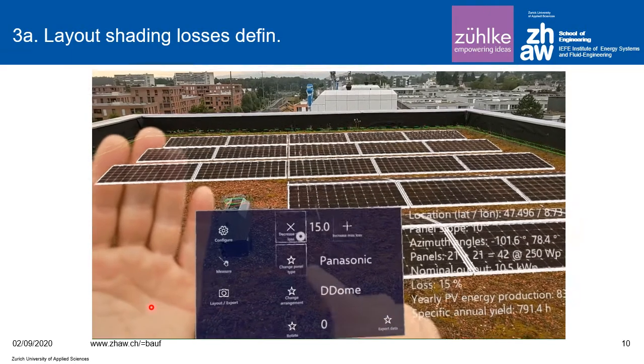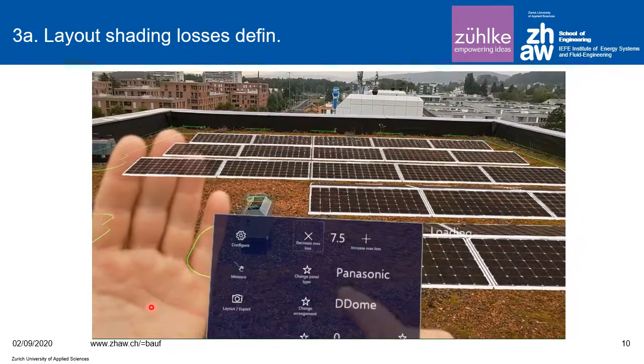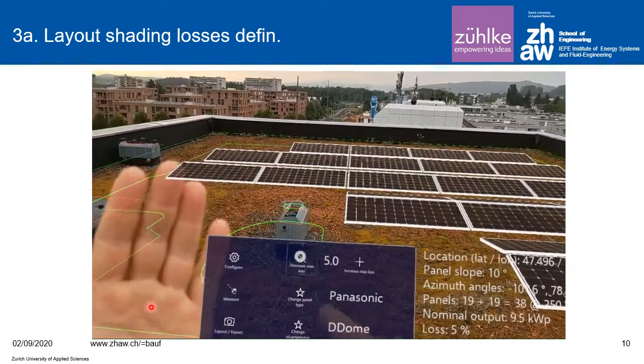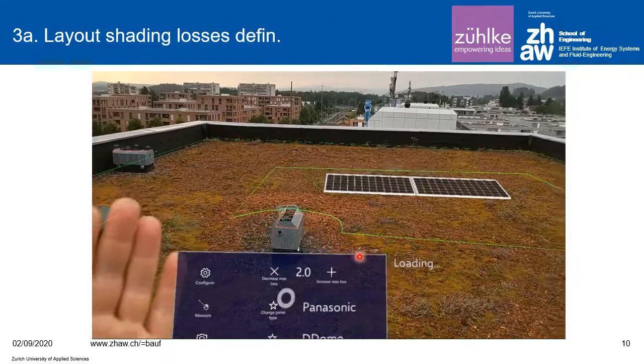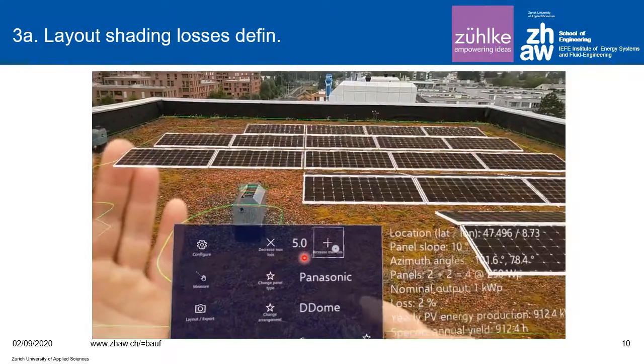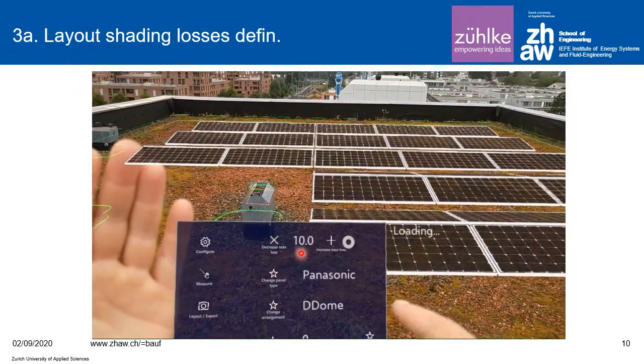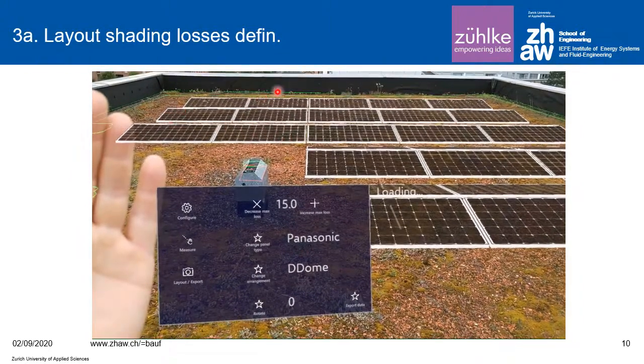We are choosing 10, then 7.5, and you can see that by changing the shading loss number — for example to 5, 7.5, or 10 — the number of PV modules automatically changes. This means right on the rooftop we can see what we want to design and plan, without having to go back to the office computer.